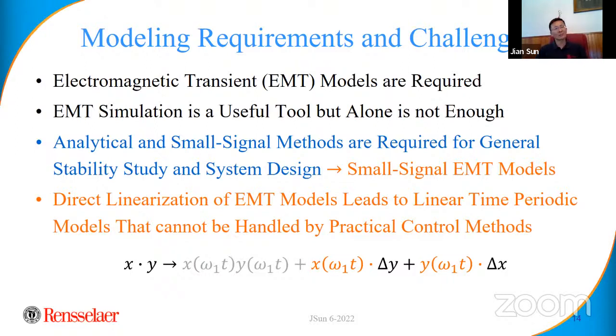But the challenge is we don't have the models. Because in today's power system stability theory, the models we use to study stability are based on the fundamental frequency model, the phasor model. You model the voltage and current by magnitude and phase angle, or frequency - you don't use the 50 hertz instantaneous variable. We only use those variables in EMT simulation. That's EMT models. For stability analysis, we don't use EMT models - we use fundamental frequency, RMS value-based models. That's what all these stability theories are based upon.